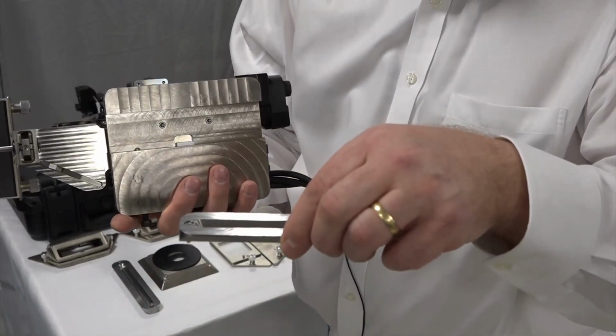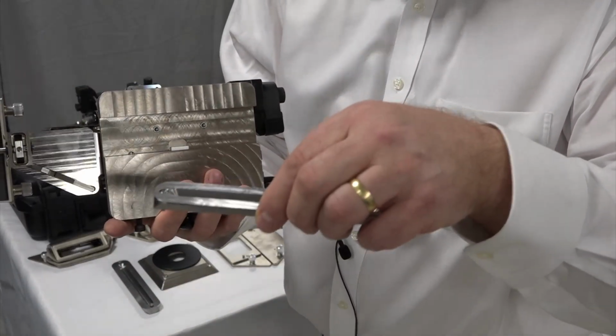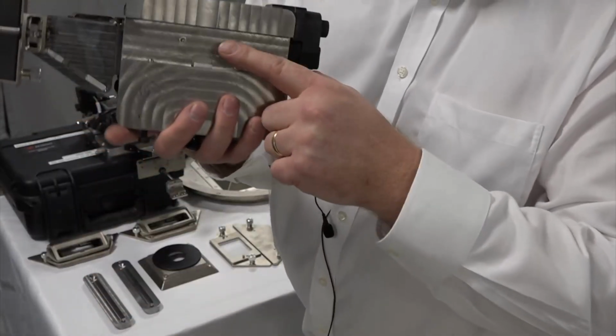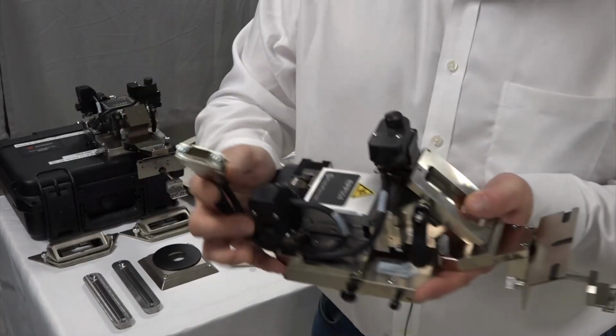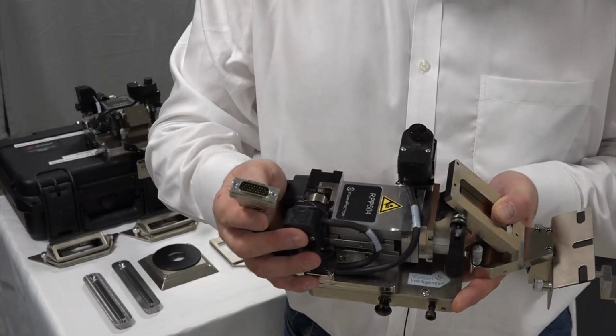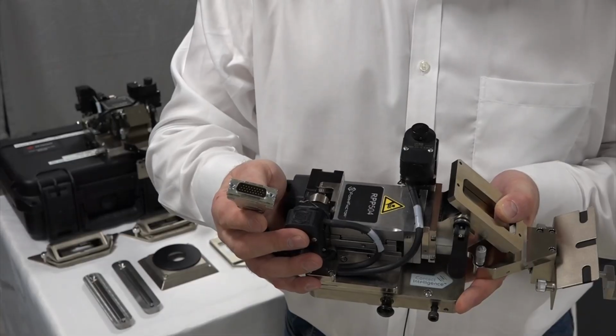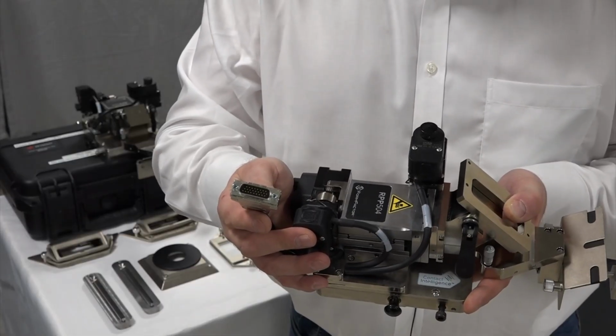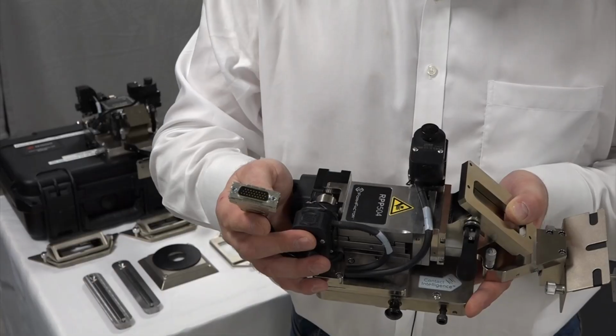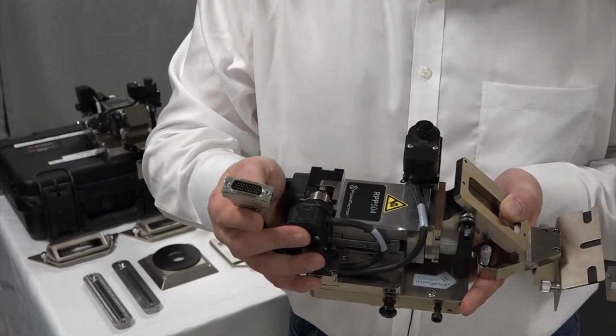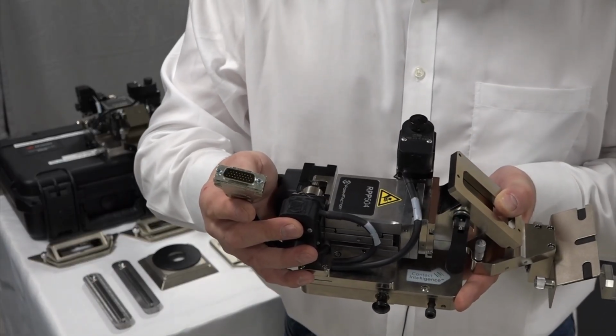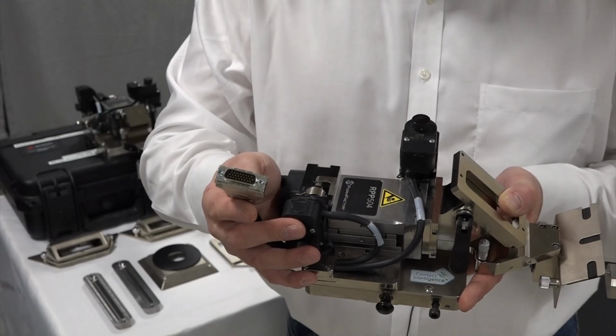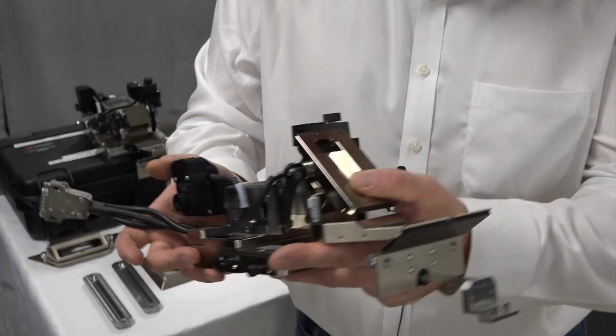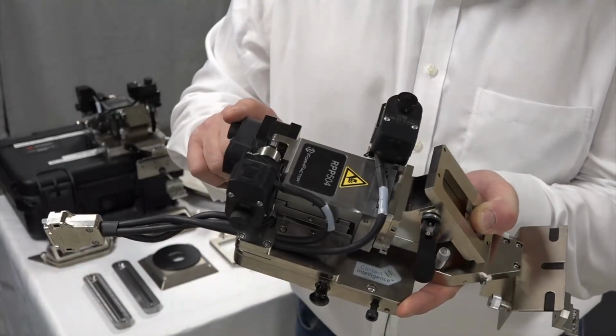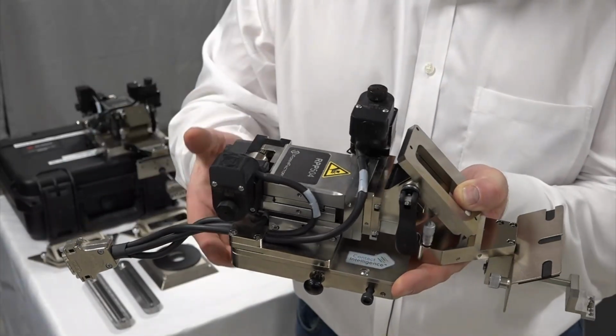The positioner base has a recess which is designed to take these V-ways. These will bolt onto the platen and enable us to clamp this positioner onto the platen. The positioner has a cable that you can see here. This cable will attach to, in the case of this probe station, the Summit 200, or in the case of a CM300, to an MPX control box. In the case of an Elite or a Summit 12K or an S300, it'll connect to an ECX box. Both serve the same function, controlling the Z, the X and the Y axes of this motorized positioner.